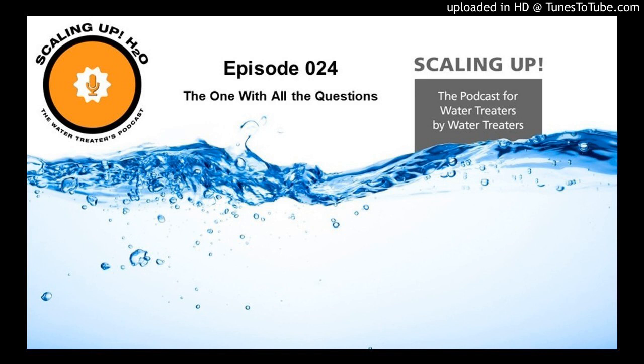And it's going to give you a number between -3 and +3. Now, 0 states that we're neither depositing nor dissolving calcium carbonate. Anything above 0 means that we're going to deposit calcium carbonate. Anything below 0, we're going to dissolve calcium carbonate.